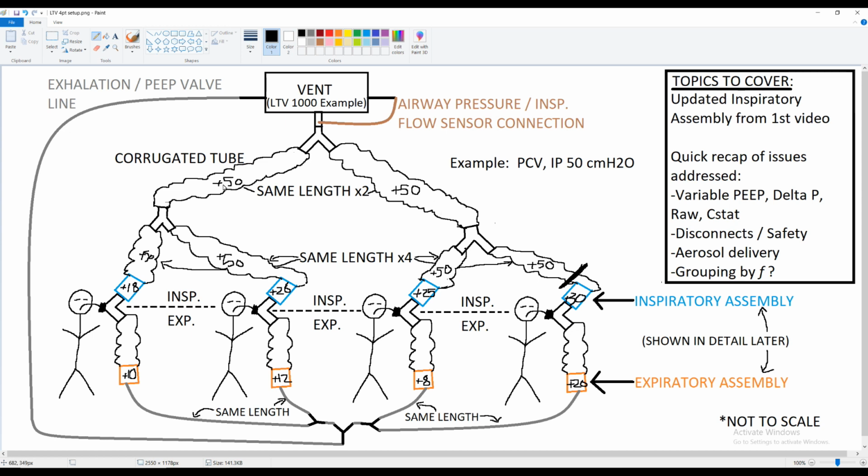And all of these patients will remain unaffected because they're not active in their inspiratory efforts. They're heavily sedated and paralyzed. It's pressure control. So at the end of the day, the ventilator is going to pressurize this tubing to whatever our target pressure is, in theory. And we're metering that pressure with each breath, and we're changing the PEEP on each patient. So we still have plenty of control. We can disconnect this patient or disconnect potentially 3 patients if we had to. Clamp, clamp, clamp, and it's still a pressure control ventilator feeding 1 patient. So that's my theory, at least on disconnects.